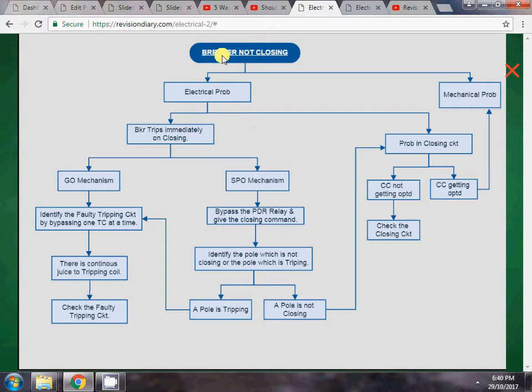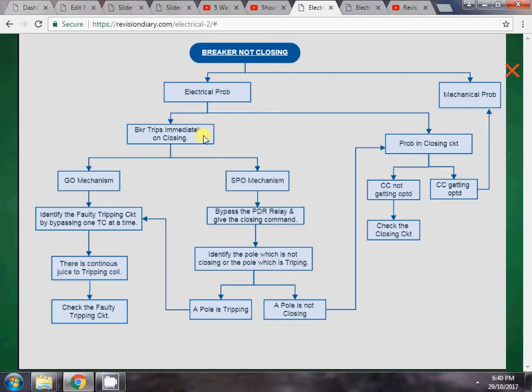This topic is about breaker not closing, which is a very common problem. It can be divided into two types: electrical problem and mechanical problem. The electrical problems we face are: first, the breaker trips immediately on closing, and second, the problem is in the closing circuit itself.